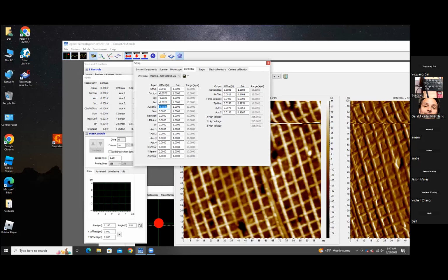And you literally do this for every one of them on your inputs to bring them to 0. I see. If they're fluctuating 1 millivolt, that's not something anybody has to stress about. That's just your DACs and tolerances. I see. Okay. So you just type in a value to counter the offset and make sure they drop to 0. And it's important to note that you do not have anything else plugged into the controller when you do this, because it will throw off your readings.